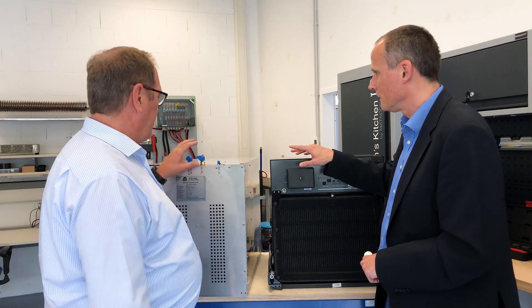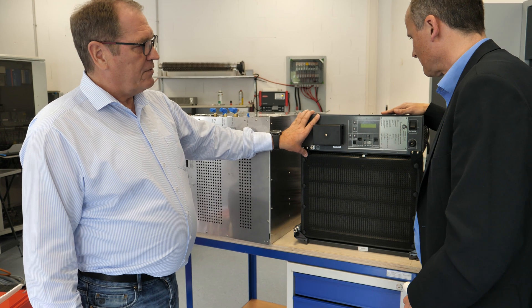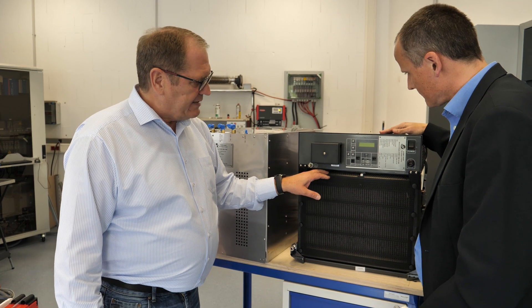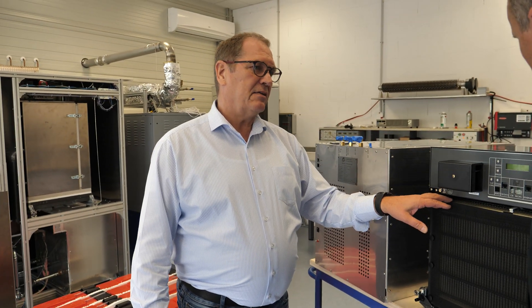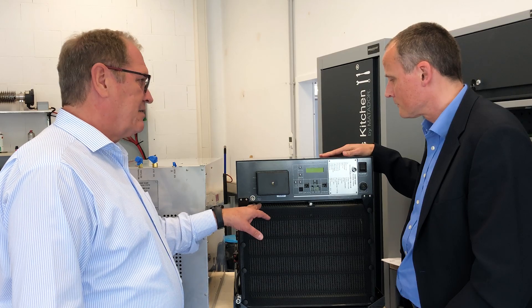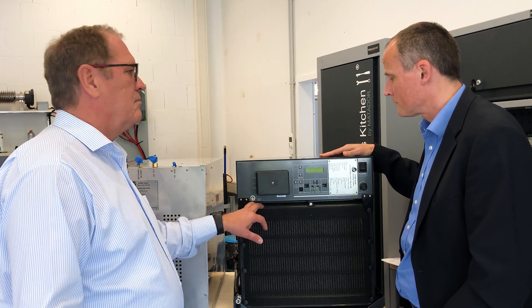How does that happen? It happens via a small pump integrated there. Here we have the actual fuel cell system – up here is the control and power electronics, and down below is the heart of this system: the stack. This is a Polymer Exchange Membrane stack – PEM – and it works with hydrogen and the oxygen from the air. We feed both into this stack: the hydrogen from the reformer as well as the oxygen from the ambient air. The reaction between anode and cathode in this stack generates the electrical power that we need for the mobile base stations.